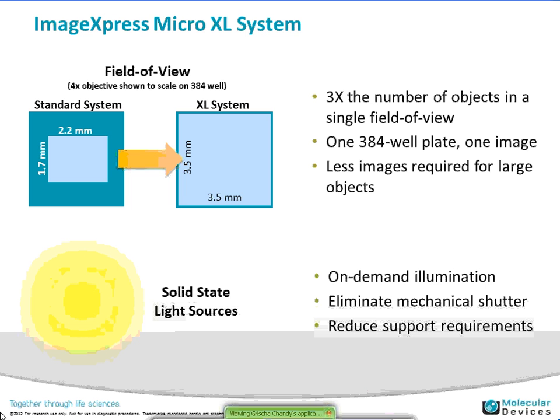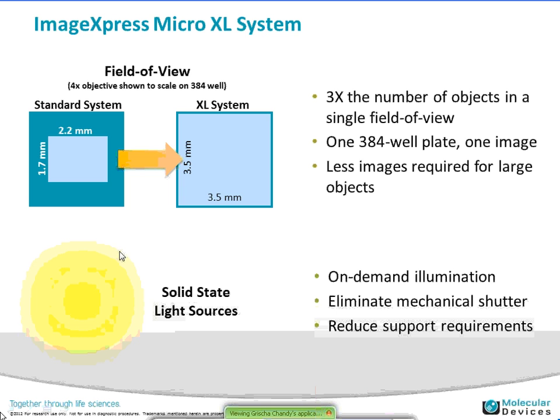One of the things that's new with the ImageXpress Micro is the XL model, which has a camera that gives you a much larger field of view. On a standard CCD system, the left shows a representative 384-well plate with the field of view inside a 4X objective. With the new XL system, you can image larger than a 384-well with a single image at 4X, essentially driving three times the speed because you don't have to stitch as many images.